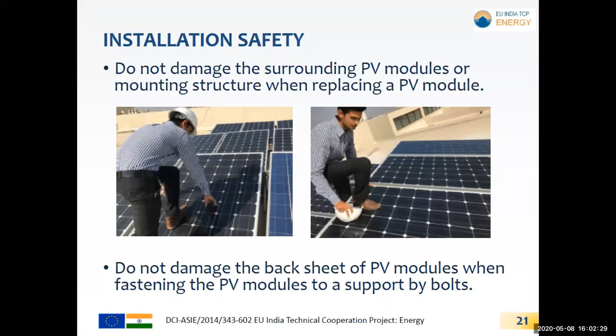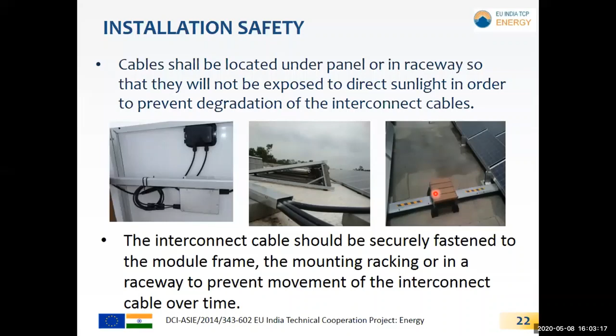Always use a conduit or a raceway to lay the cable on the terrace, so the direct sunlight will not expose the cable and it prevents degradation of the cable insulation. In the first picture, you can see the cable is fastened to the module frame. In the second picture, the cable is laid through the cable raceway or cable tray. And in the third picture, you can see there is a footstep which can protect the cable tray.